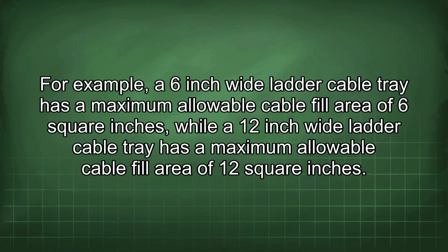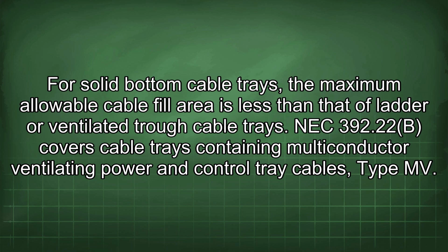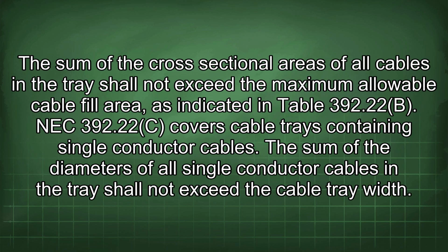For example, a 6-inch wide ladder cable tray has a maximum allowable cable fill area of 6 square inches, while a 12-inch wide ladder cable tray has a maximum allowable cable fill area of 12 square inches. For solid-bottomed cable trays, the maximum allowable cable fill area is less than that of ladder or ventilated trough cable trays. NEC 392.22(B) covers cable trays containing multi-conductor power and control tray cables type MV. The sum of the cross-sectional areas of all cables in the tray shall not exceed the maximum allowable cable fill area, as indicated in Table 392.22(B). NEC 392.22(C) covers cable trays containing single-conductor cables. The sum of the diameters of all single-conductor cables in the tray shall not exceed the cable tray width.